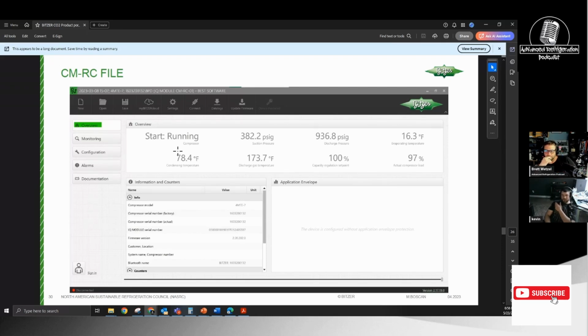So I started looking, and it's some janky block calculation in there. I'm like, this calculation's wrong. It's backwards. They have it where it's true for the last line. So it threw it as true because of the way they had the lines of logic, and then they had true at the end. The lines of logic were OR, and neither one of them was on for the low calc for low suction pressure or high suction pressure, and then they had true at the end. It just threw true and turned it on. So I'm like, this is weird. This is wrong. So I pull up the 255s, and sure as shit, it's the same way. I'm like, oh, this has been running in switchback for forever. That's not good. So all three racks were like that.